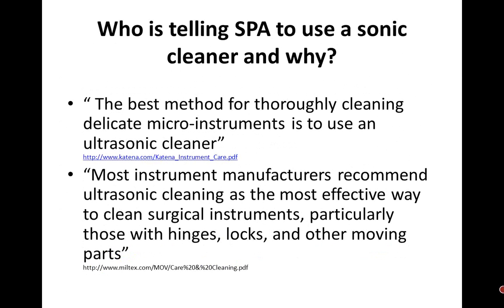So who's telling the sterile processing area, or the SPD as I call it at times, to use a sonic cleaner and why? I've only taken 2 examples out of the many, many instrument manuals. In those instrument manuals, in the IFU or in the part of the catalog or manual, it says the best method for thoroughly cleaning delicate micro instruments is to use an ultrasonic cleaner. Most instrument manufacturers recommend ultrasonic cleaning as the most effective way to clean surgical instruments, particularly those with hinges, box locks, and other moving parts. So if you're buying surgical instruments and you read the IFU or you open up the catalog or the manual, they're probably going to be talking about using a sonic cleaner in some part of that cleaning process to get that medical device clean and functional.